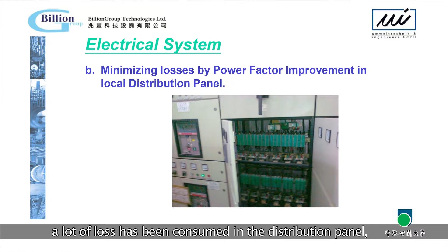One significant waste is in the power distribution, not outside the factory, inside the factory. Because they only install the capacitor in the main board. Installing the capacitor in the main board is good for power distribution, but only from the perspective of the supply company. There's no benefit internally. Once the client adopted my advice to install power factor correction in the load center, they could immediately save a lot of energy running from the main board to the load center.